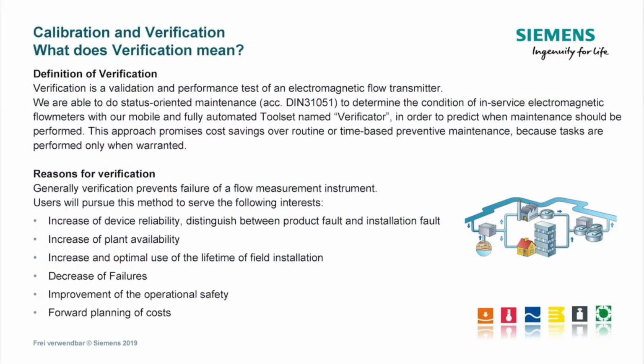What does verification mean? Verification is a validation and performance test of an electromagnetic flow transmitter. Siemens is able to do status-oriented maintenance, in accordance with DIN 31051, to determine the condition of in-service electromagnetic flow meters, with the Siemens mobile and fully automated toolset named Verificator, in order to predict when maintenance should be performed. This approach promises cost savings over routine or time-based preventive maintenance, because tasks are performed only when warranted.